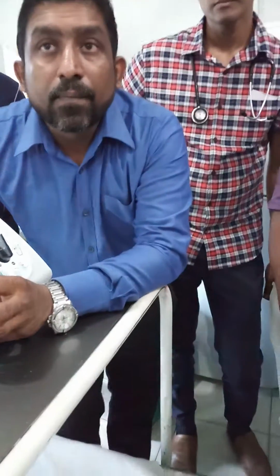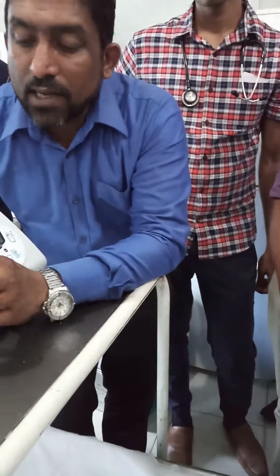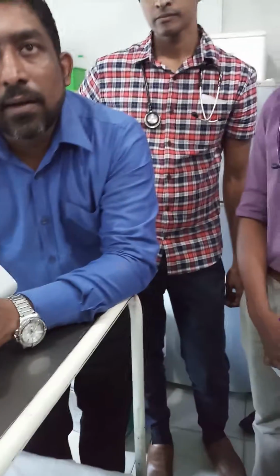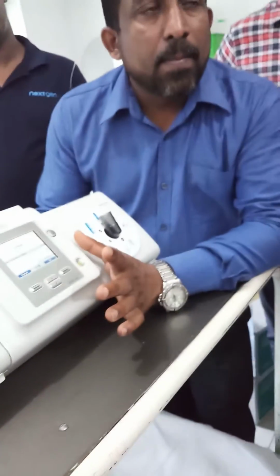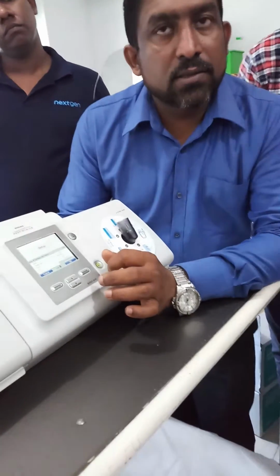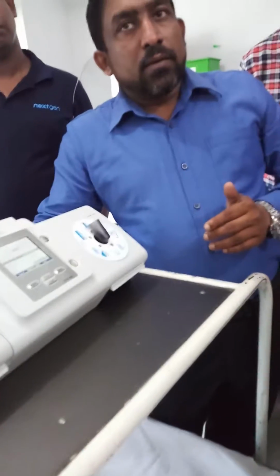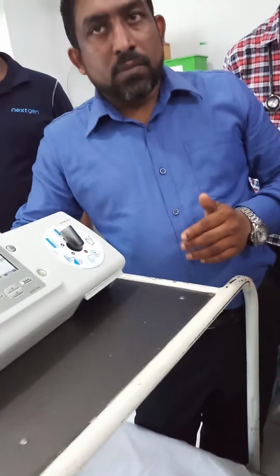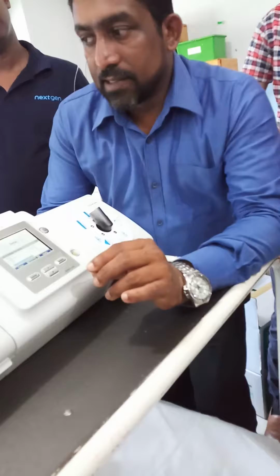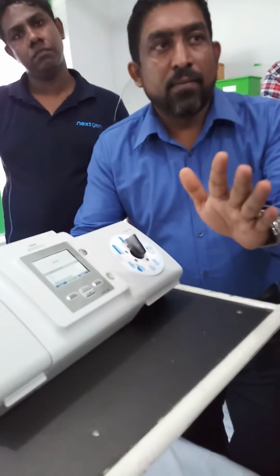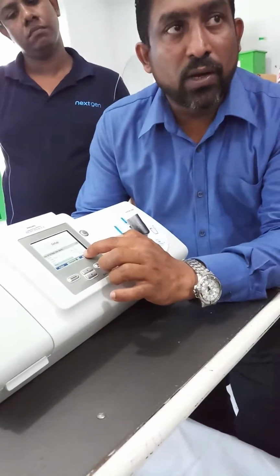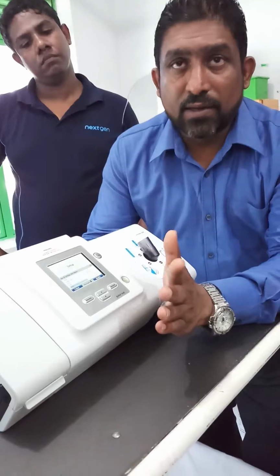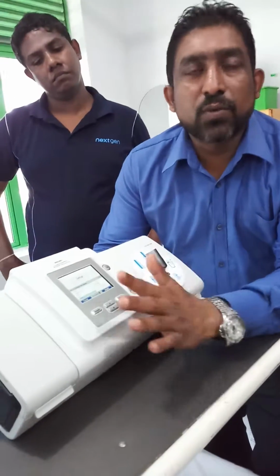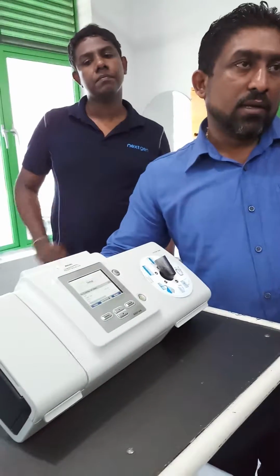Normally for an adult, how much do we keep the IPAP? Normally you can go up to 40 on this IPAP, but for pediatric, 20. It depends on the doctor's consultation. It's up to the doctor how to change the IPAP, depending on the disease. Sometimes the maximum alveolar pressure for an adult is that much. Normally in NIV they say don't go beyond 8 EPAP, but here you can go EPAP up to 12, 14, 16. It differs with the patient's situation. According to the patient's situation, you can change it under the doctor's guidelines.